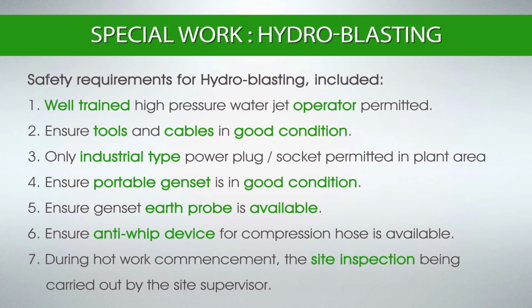There are some safety requirements for hydroblasting, including: 1. Well-trained high-pressure water jet operator permitted. 2. Ensure tools and cables in good condition. 3. Only industrial-type power plug socket permitted in plant area. 4. Ensure portable genset is in good condition. 5. Ensure genset earth probe is available. 6. Ensure anti-whip device for compression hose is available. 7. During hot work commencement, the site inspection being carried out by the site supervisor.